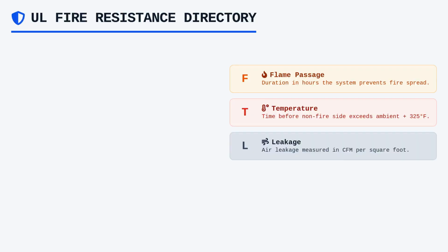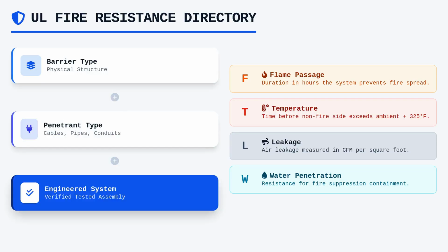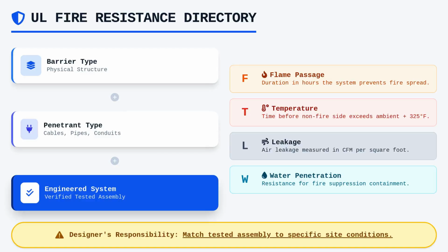Smoke leakage is critical for life safety, evaluated via the L rating, representing the amount of air leakage in cubic feet per minute per square foot. Furthermore, the W rating identifies a system's ability to resist water penetration, which is vital when addressing modern building code requirements for fire suppression system containment. Every combination of barrier type and penetrant requires a specific engineered system, and it is the designer's responsibility to find a tested assembly that matches their specific site conditions.